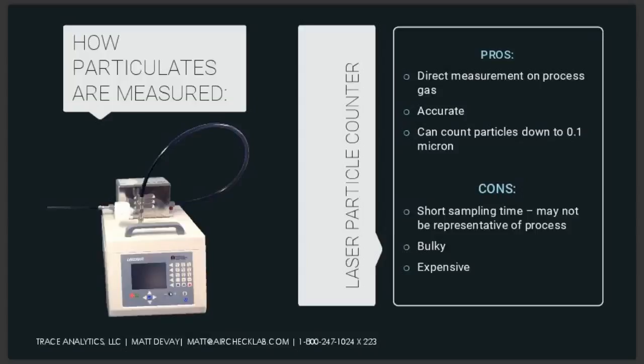The results that you get out of an LPC are very close to a direct representation of the system at that time or at that moment. But remember, going back a few slides, these systems are dynamic. That may or may not actually be how your system's performing over a longer period of time or as a reasonable average. They are highly accurate instruments. They can count particles down to 0.1 micron. So why wouldn't you use one? Well, as mentioned, you're not necessarily getting anything more than a snapshot of your system for a very short window. Not necessarily a good representation of average performance.